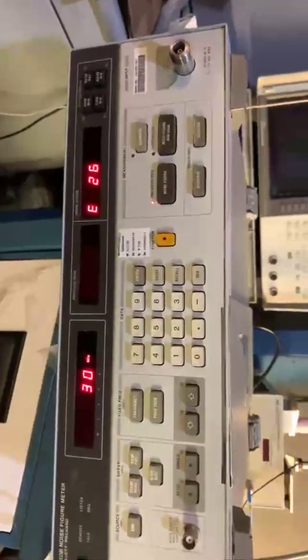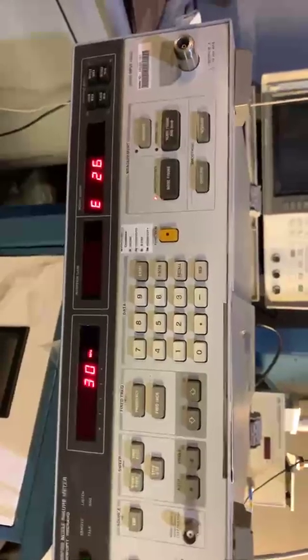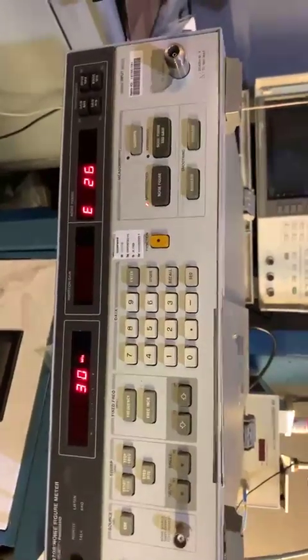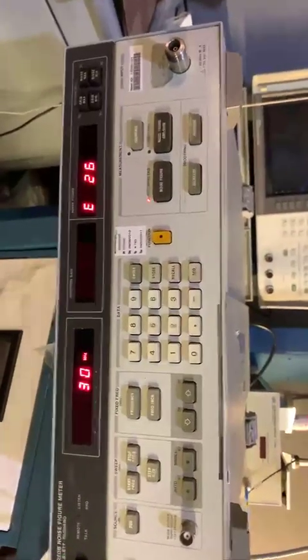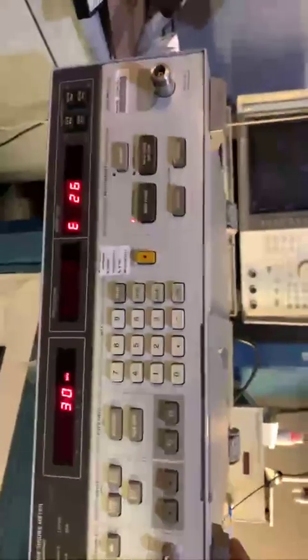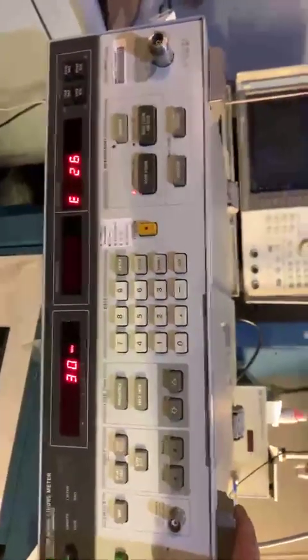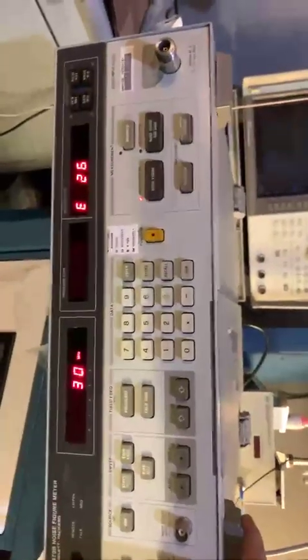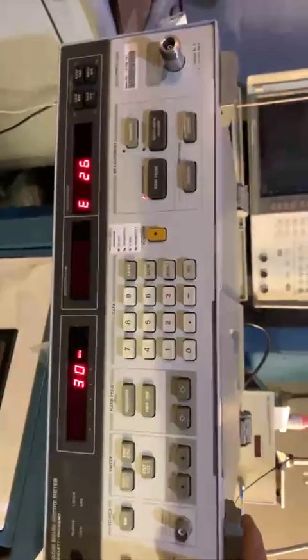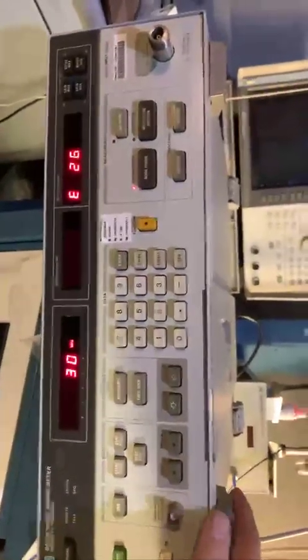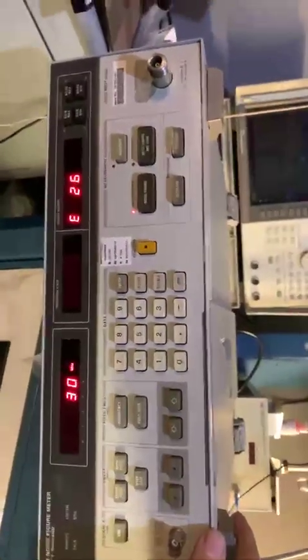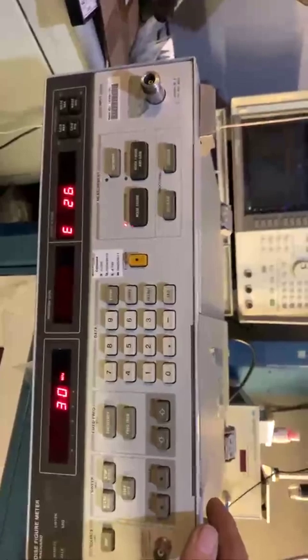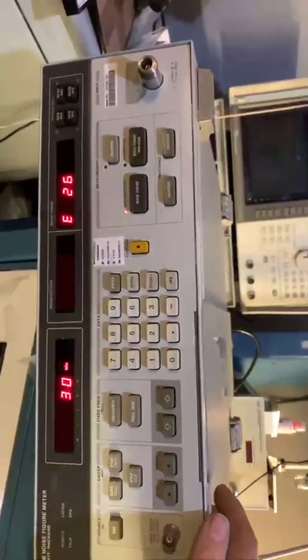So now, of course, the next question you're probably going to ask is, how do I get rid of E26? And unfortunately I can't show you right now, because I don't have a noise source, I don't have a 346B, because what you need to do is recalibrate the IF attenuators. And basically the way you do this on this meter is you have to have a noise source with 15.2 dB ENR, and you have to enter the ENR values into the meter, store them, and then you just connect the noise source here to this RF input, the 28 volt drive, and you simply initiate the IF attenuator calibration, which is special function 33, if I'm not mistaken.